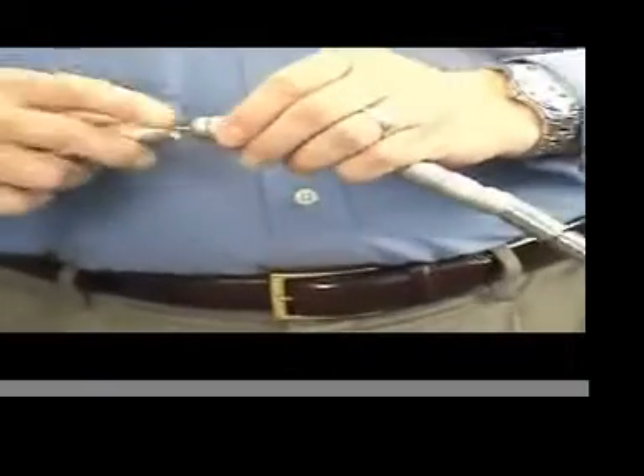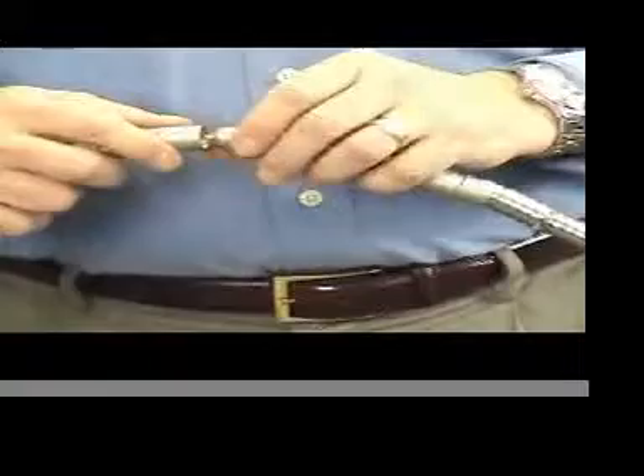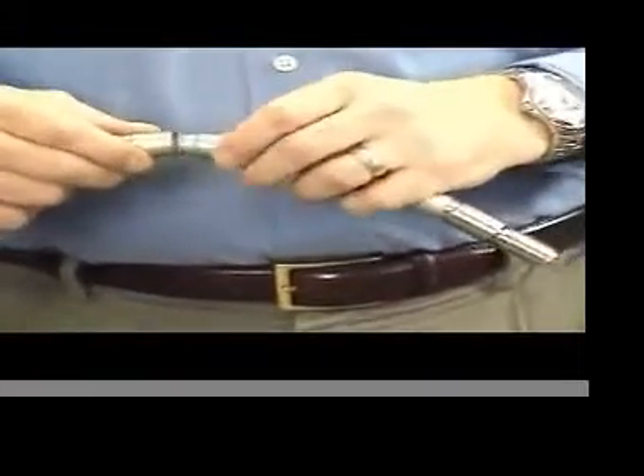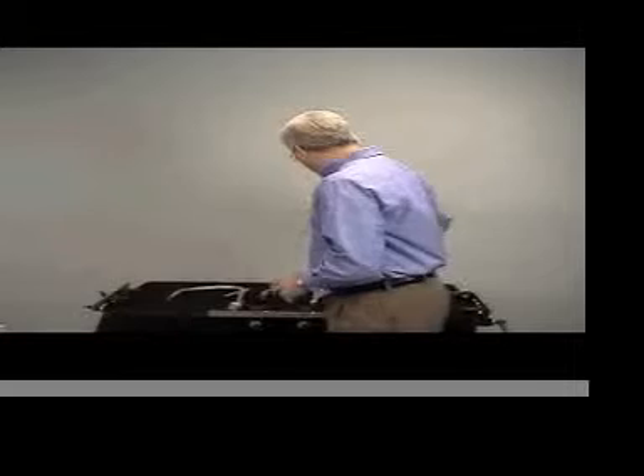All Mediflex flexible arms consist of a series of knuckles, or ball and socket joints, that are built around a twisted wire cable. When the cable is loose, the arm is very movable and can be positioned in virtually unlimited numbers of positions. When the cable is tightened, tension is applied to each joint, and the friction causes the joints to resist movement. Now, each of the three arms we looked at has its own tensioning knob.